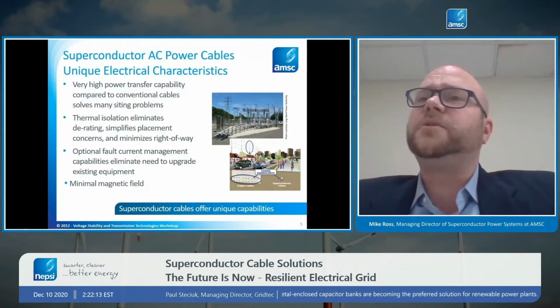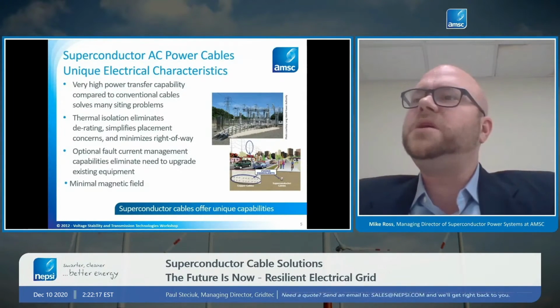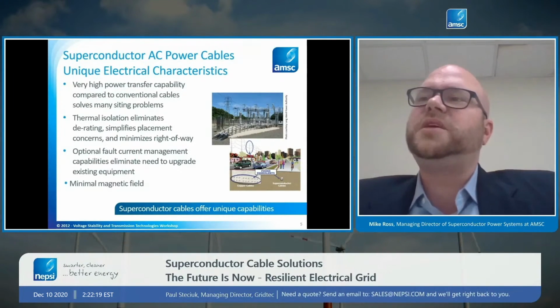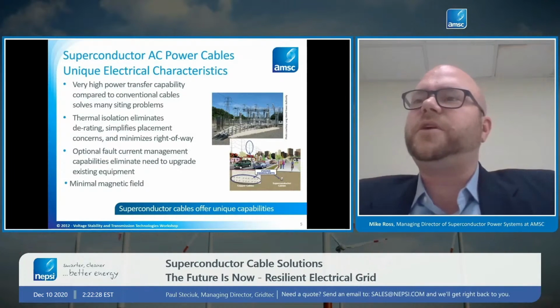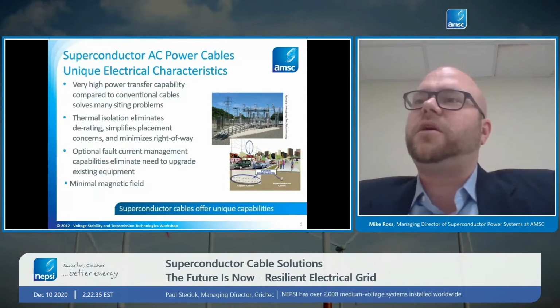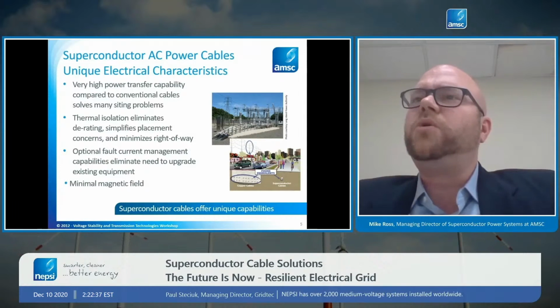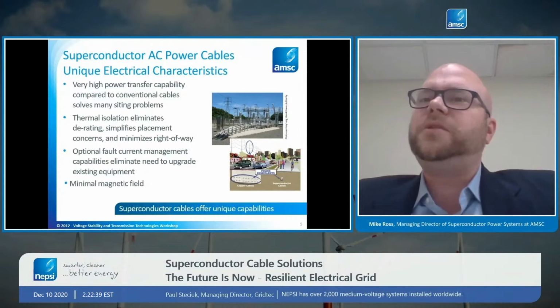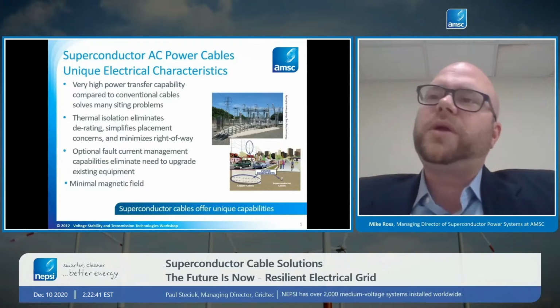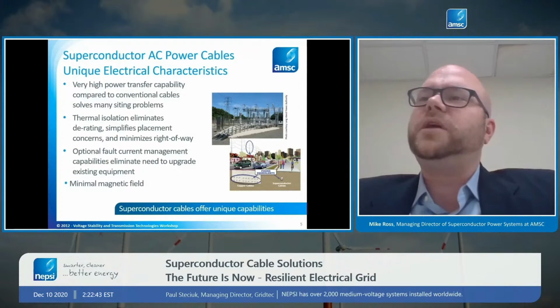With superconductor cables, we're cooling the cables internally with liquid nitrogen. What that means is there's no heat exchange with the outside world. The cables can be put very deep underground without any need to derate them. You can put multiple cables very close together. You can put them next to steam pipes or other power cables that are already in the grid, and it won't be impacted by the heat coming from those cables, and it won't create heat that will impact the existing equipment.